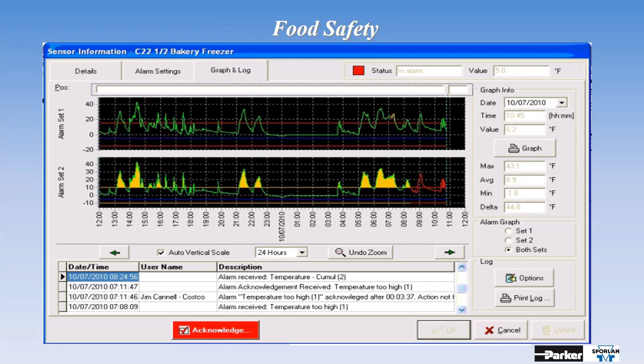Okay, let's go into the nodes themselves. I'm going to go over the 500 and I'm going to go over the 700. Nate, you're going to have a lot of stores with the 500 in it because you've been using MicroThermo for a long time. That's why I want to do this segment here. So the MP500 is configurable. That means I can program it to be an HVAC node, a refrigeration node, a lighting node, an energy node, a VFD node, a chiller skid node, a leak detector node, whatever you want it to be, I can make that be that.